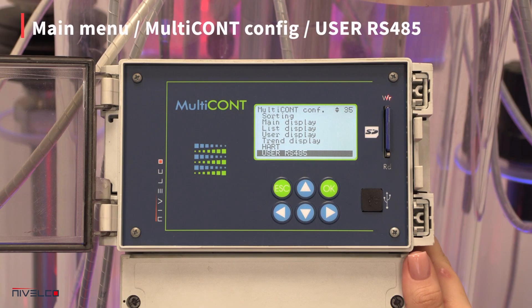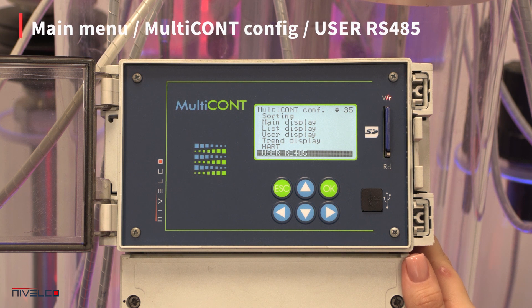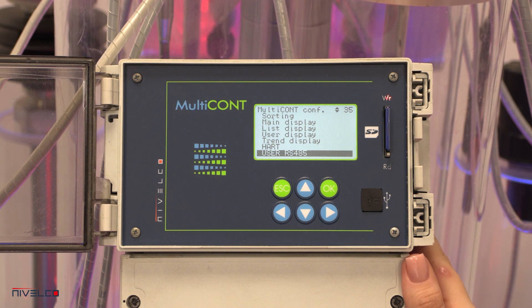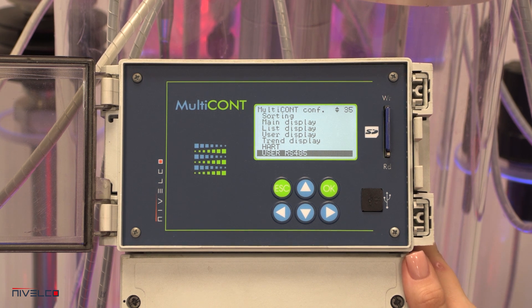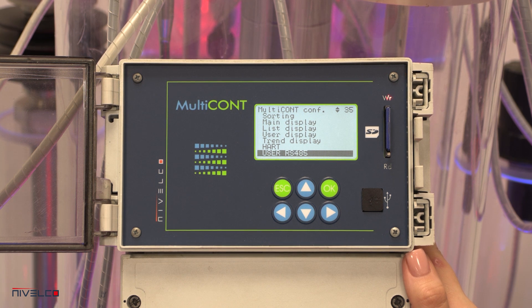The RS-485 interface provides serial data transfer to the central process controller computer or PLC. Each Multicont unit has a unique address, so up to 30 units can be connected in a system.